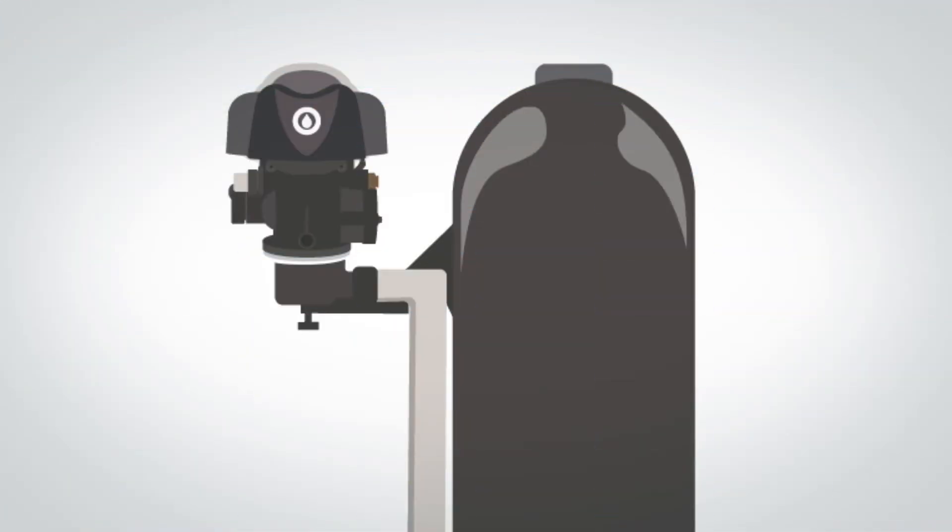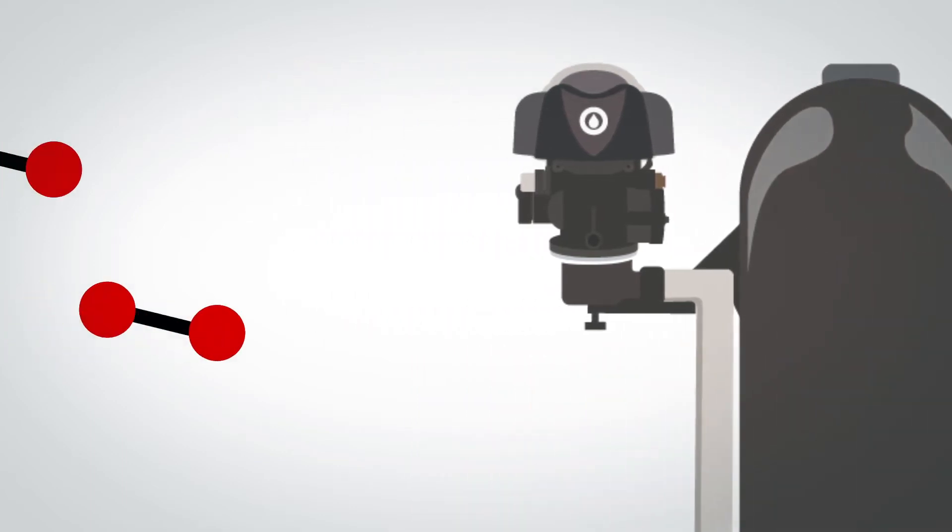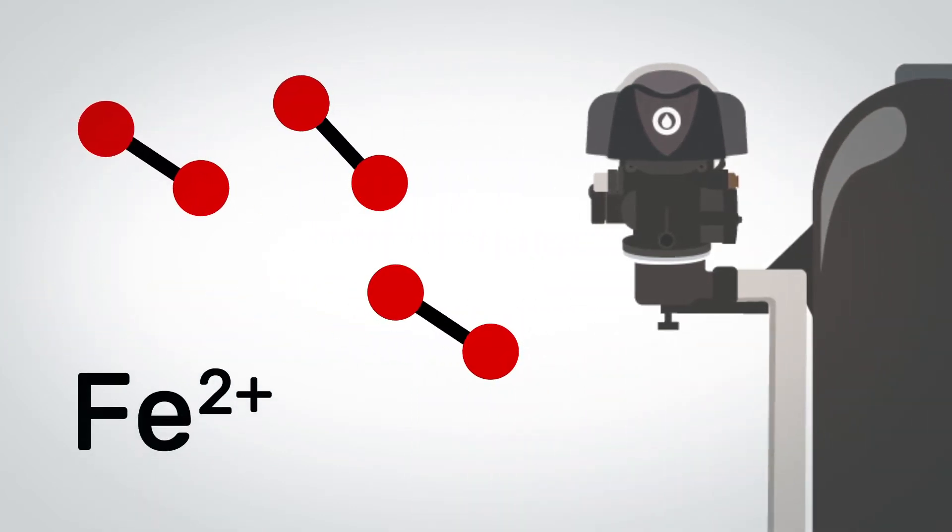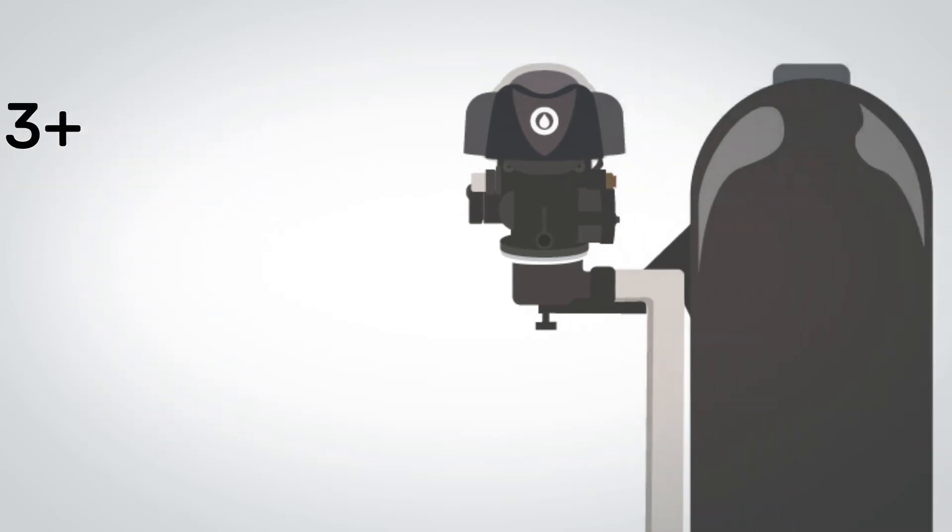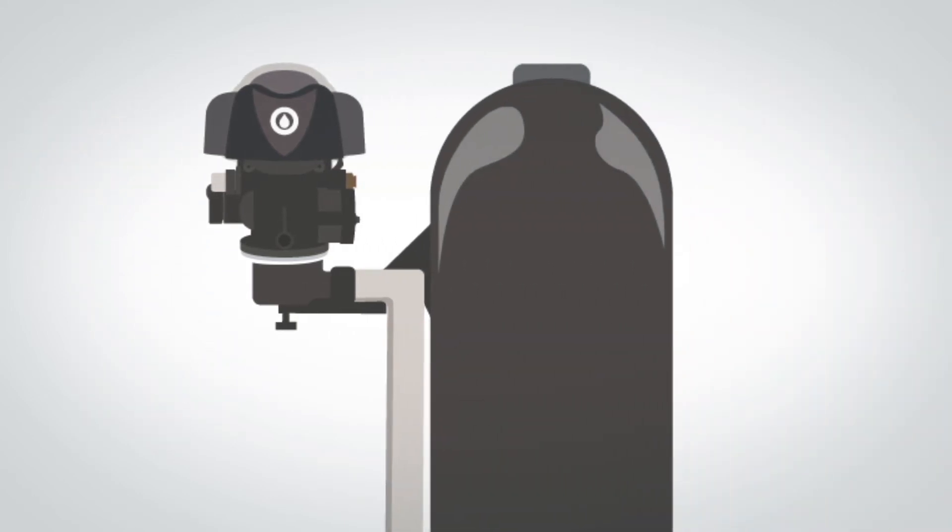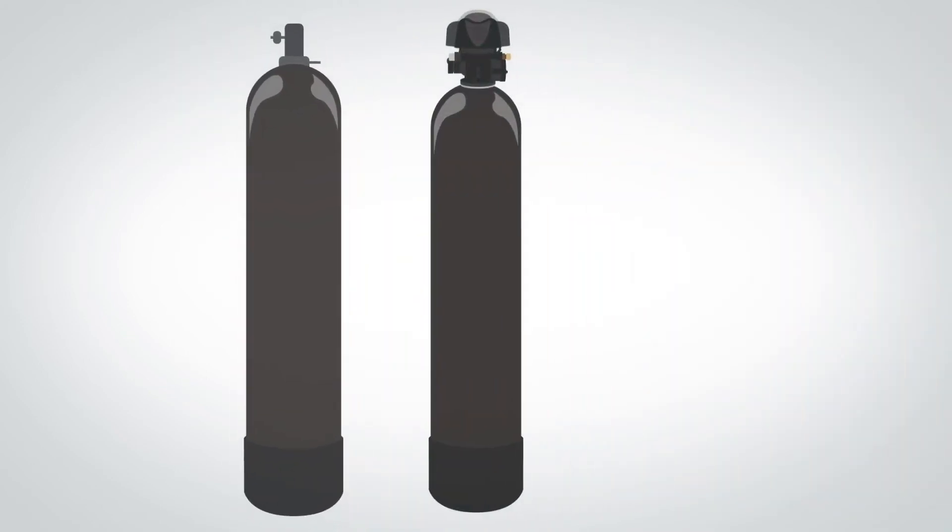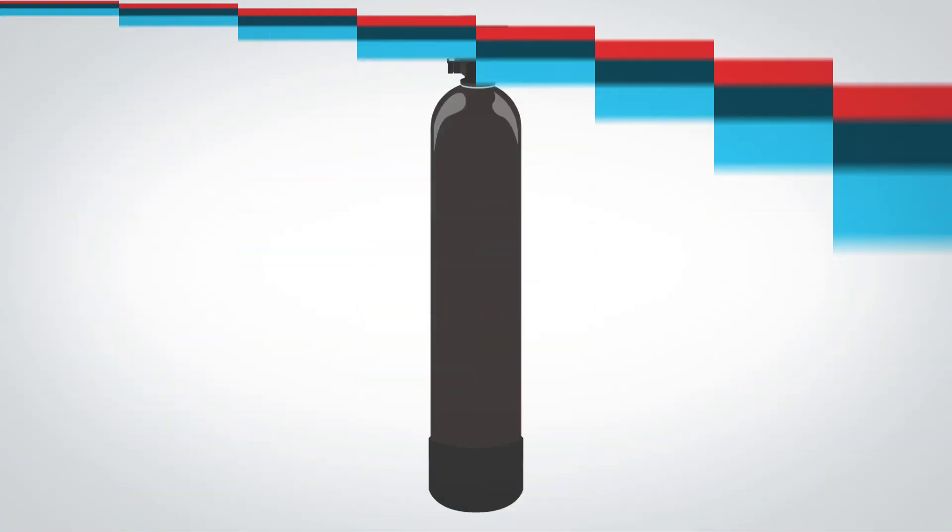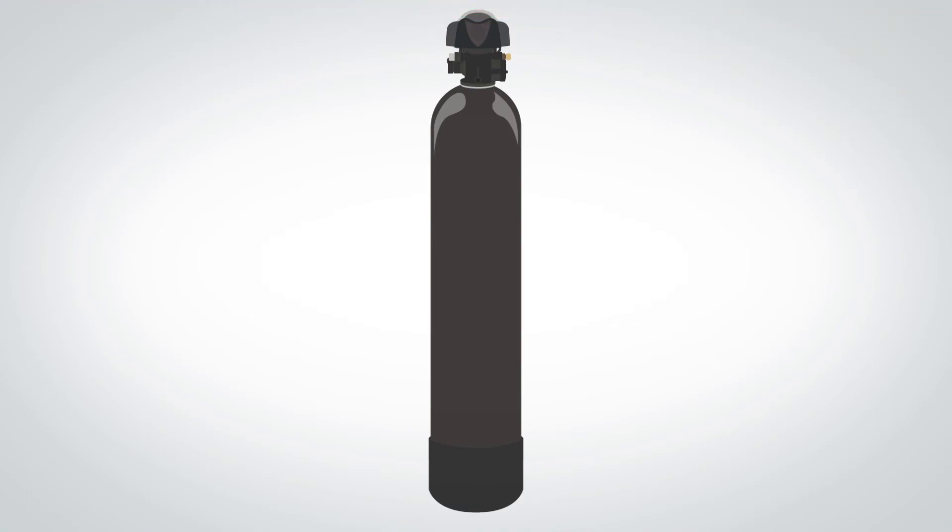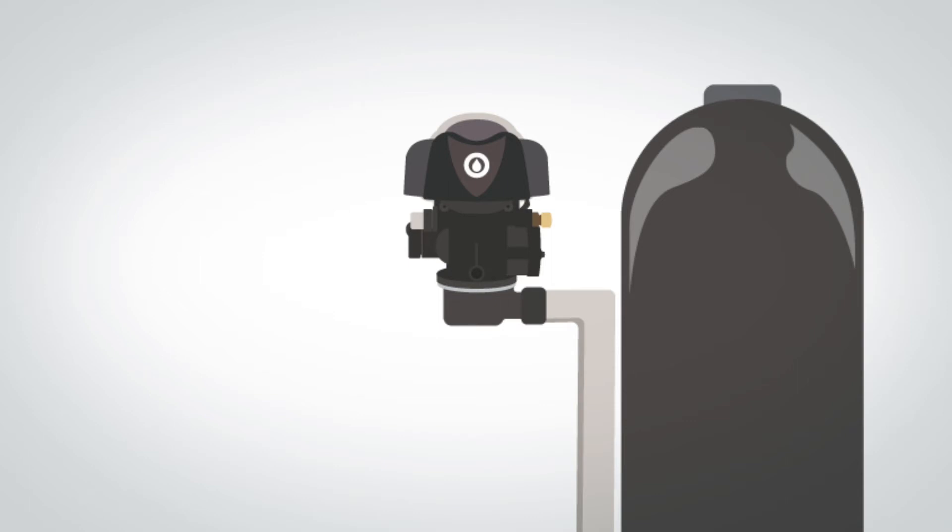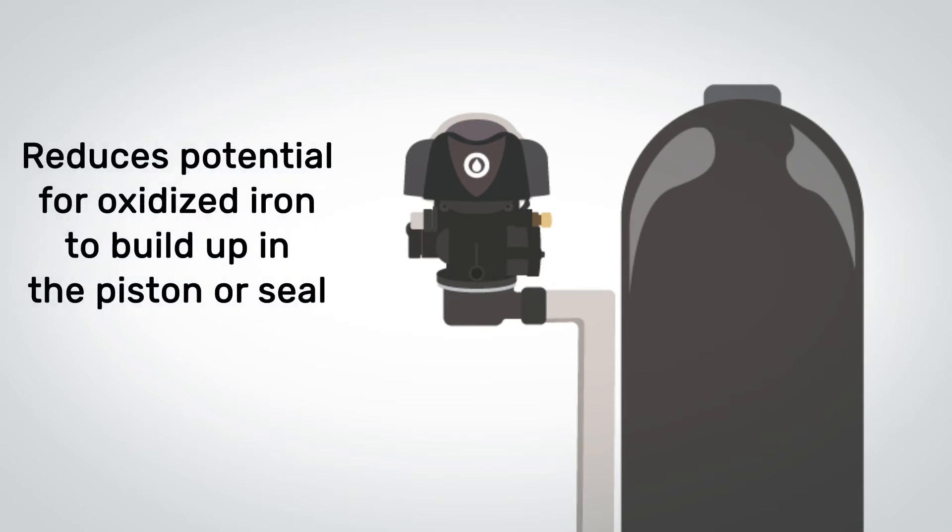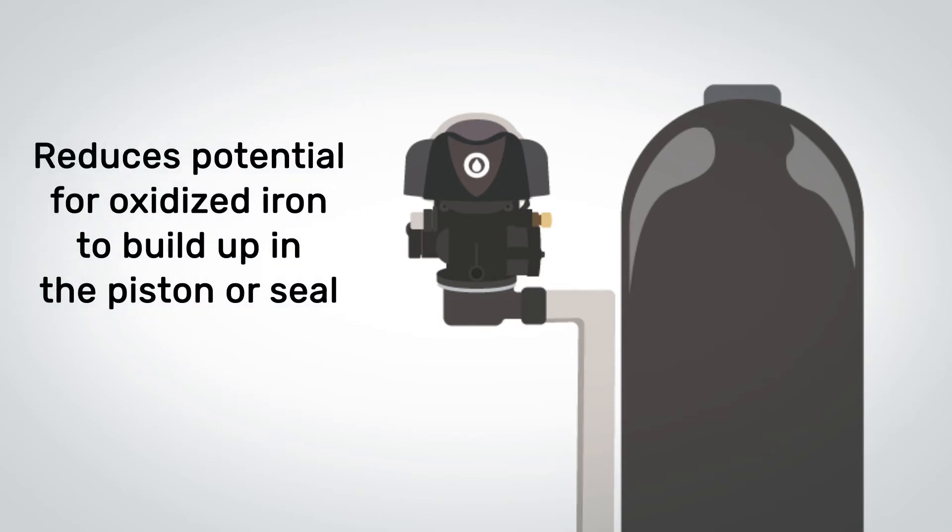The single tank aeration filter receives its name due to the fact that it uses air to convert clear ferrous iron into ferric iron so that it's able to be filtered out by the media bed, and it does this all in one tank as opposed to a system that would require separate tanks for aeration and filtration. While many manufacturers offer single tank aeration filters, only our system separates the control valve from the top of the tank, which reduces the potential for oxidized iron to build up in the piston and seals in the valve body.